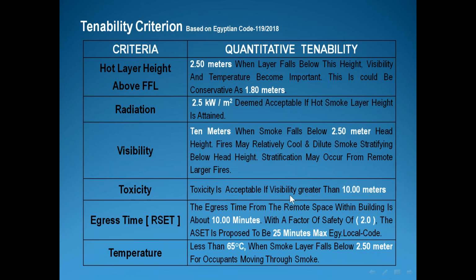So simply here we consider, in Egypt, that if the visibility is greater than 10 meters, and normally we use 30 meters, all these hot gases are still far away from the people. The egress time from the remotest space within the building is about 10 minutes with a safety factor of 2. This is the maximum factor of safety, double. The available safe escape time is proposed to be 25 maximum. This is for the Egyptian local code. I don't know what these values are; you can get them from the civil defense or the fire brigade officers.